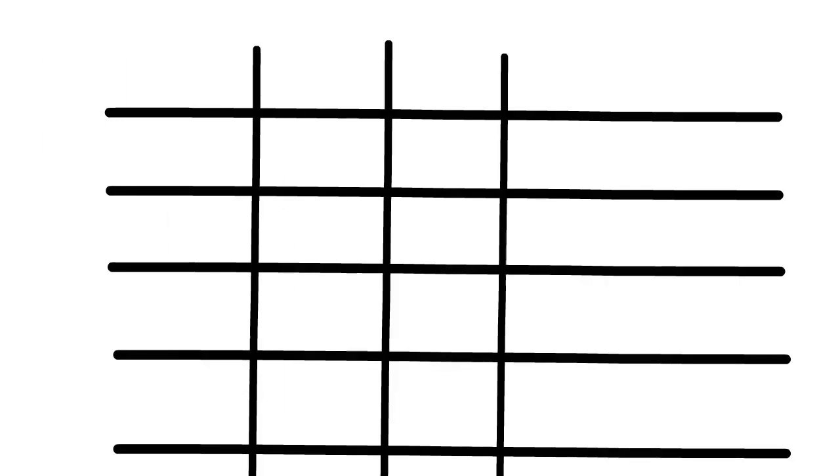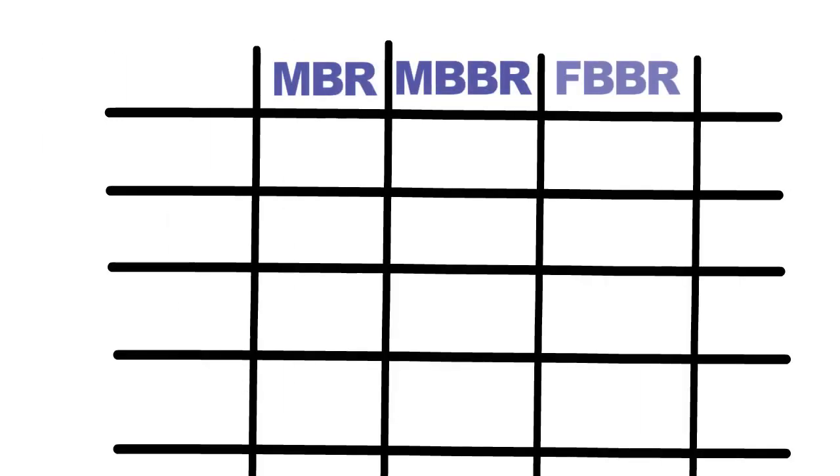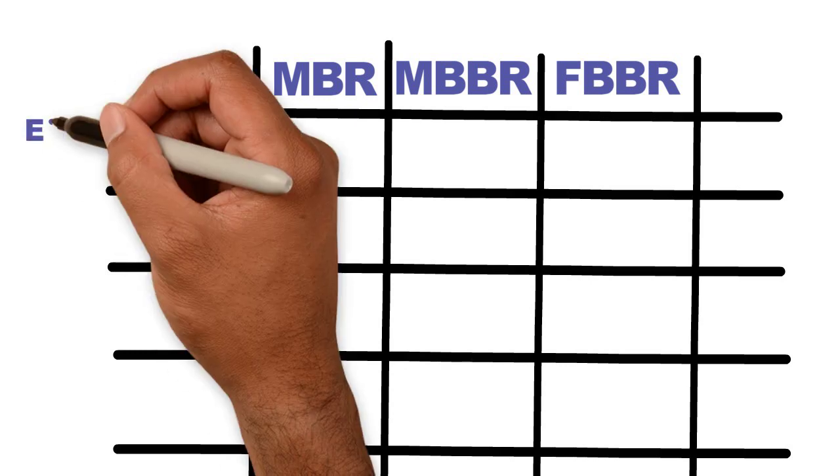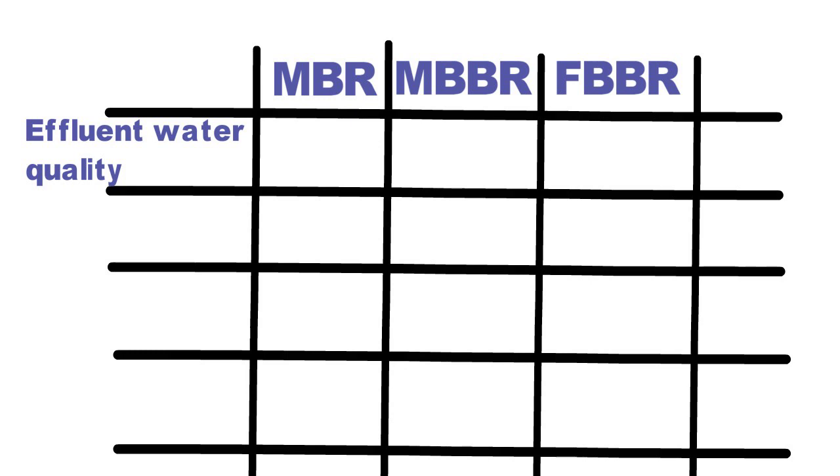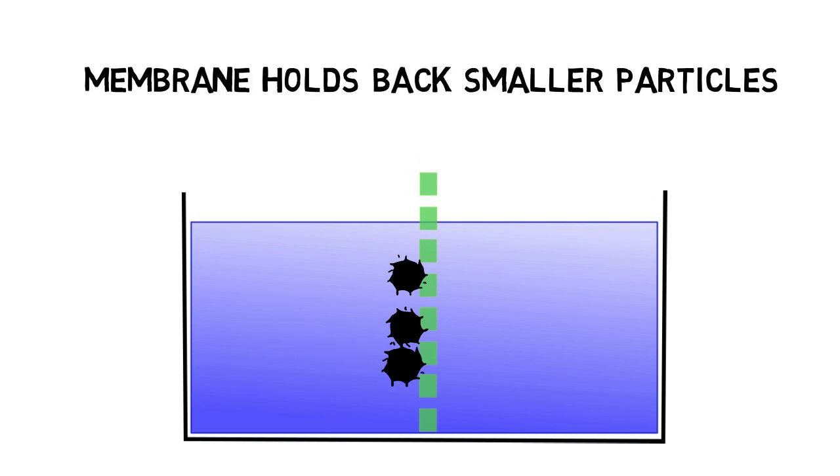The comparison of the three systems showed different advantages and disadvantages for industrial wastewater applications. Effluent water quality: MBRs show in general a slightly better BOD removal than MBBRs or FBBRs. Very fine membranes can even hold back germs so that the water effluent quality is in general better.